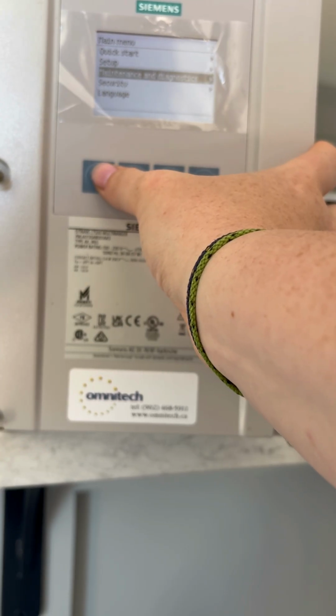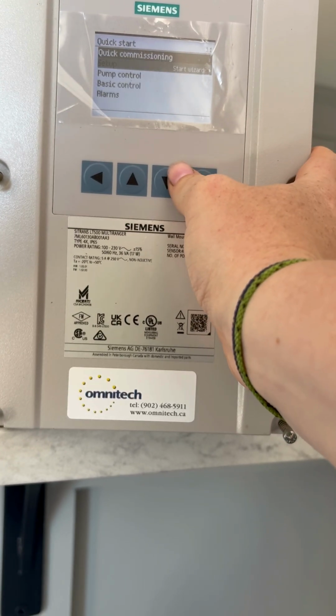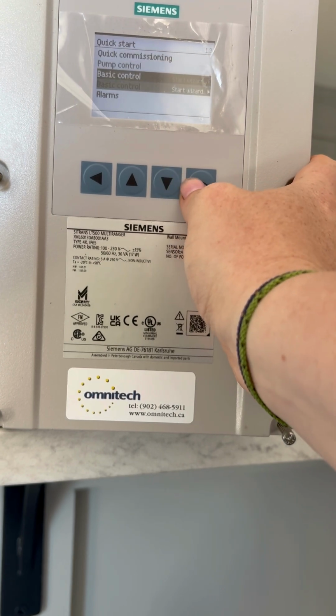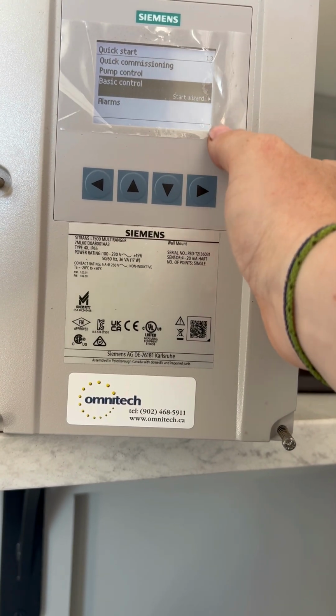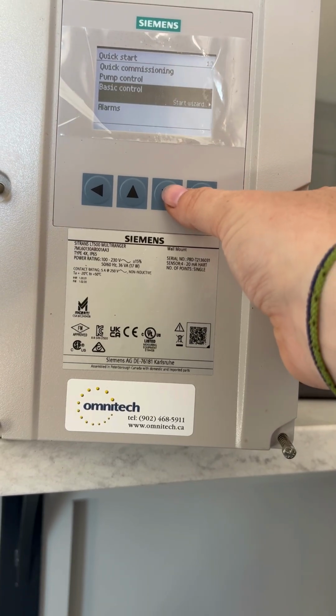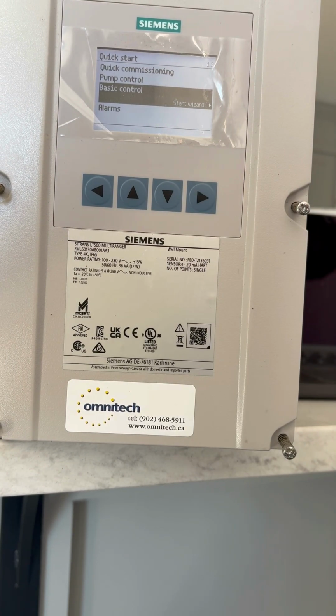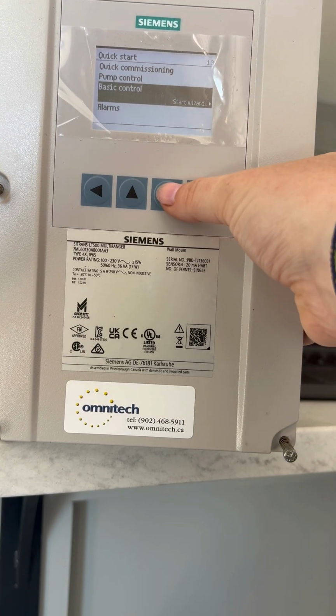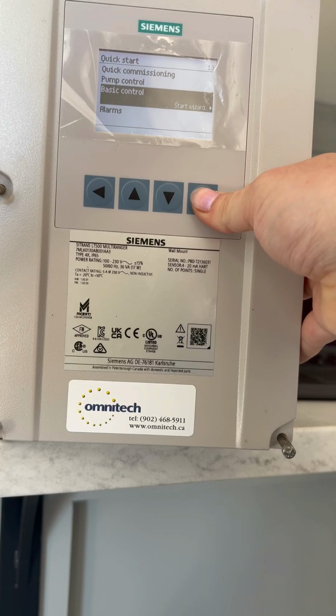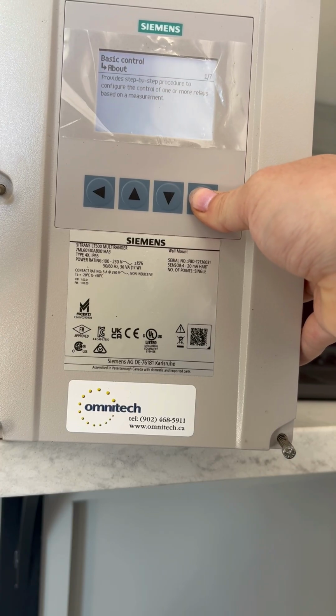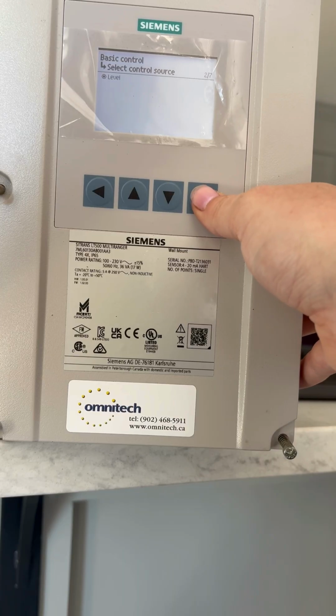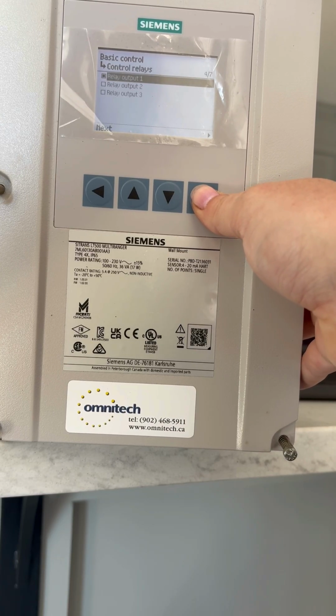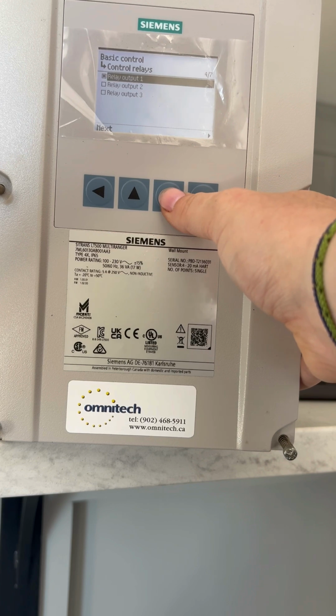And then if I want to set up, for example, just quickly into the relays. So basically I'm going to go into basic control. So again, quick commissioning is what we went into in the very beginning. Then we have pump control, basic control, and alarms. If we were using a pump, or multiple pumps, you do this quite often in lift stations for water, or wastewater, and applications like that. We could set up multiple pumps and have it on and off. But basically, we just want to turn that solenoid on and off in this application. So we're going to go into basic control. Again, I'm clicking right. Basic control for level. Relay output 1. That's what I want to go into.